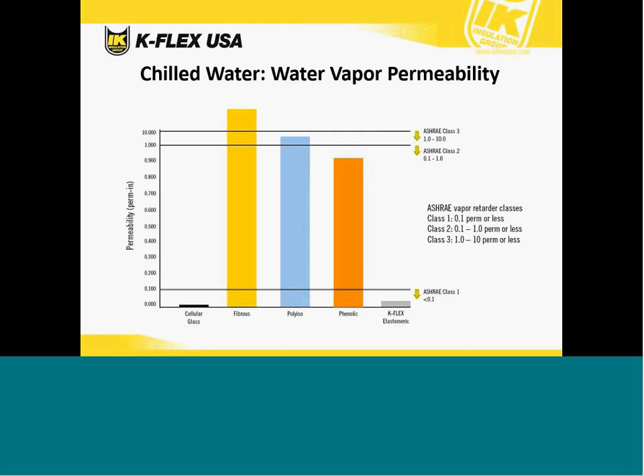Again, showing the water vapor permeability of several different insulation types. On the left here, you see cellular glass with a permeability well below the ASHRAE Class 1 line. Next to that is an unjacketed fibrous insulation that has a permeability around 5. Further, you have polyiso, which has permeability slightly over 1, which is between ASHRAE Class 2 and 3 vapor retarder. After that, you've got the phenolic, slightly below 1, and then finally K-Flex Elastomeric, which is below 0.1, ASHRAE Class 1 vapor retarder.